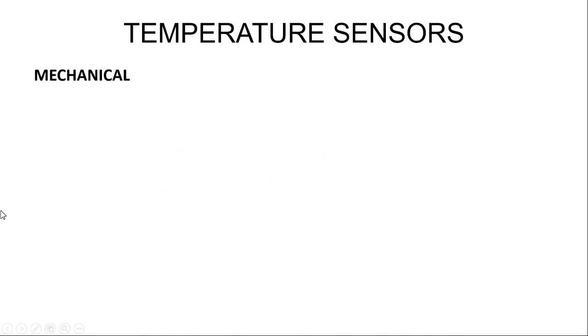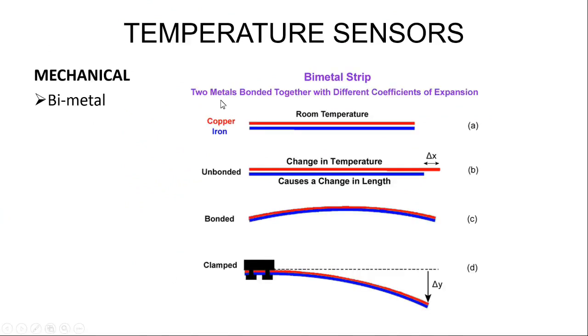First, we'll talk about the mechanical type of temperature sensors. The first basic one is bimetal. Two metals bonded together with different temperature coefficients of expansion. So you have copper and iron strips of equal lengths at room temperature. When they're unbonded but heated, copper will expand greater than the iron will. Now, if you bond them together, obviously it would bend. You clamp one end down and have the other end as the actuating end, then this can be used to operate a plunger, two contacts, and so on and so forth.